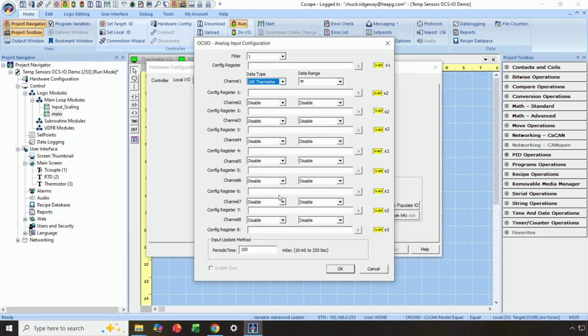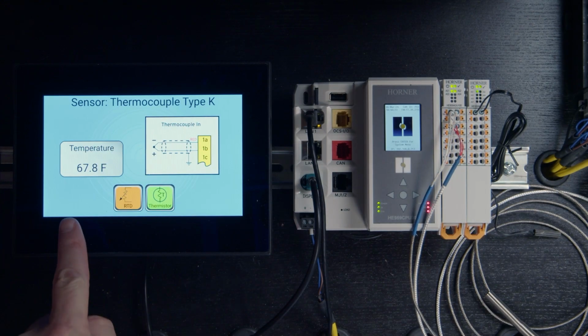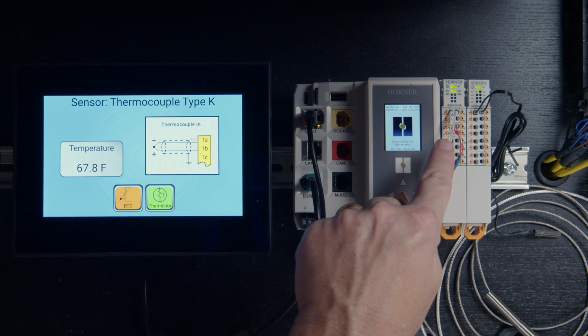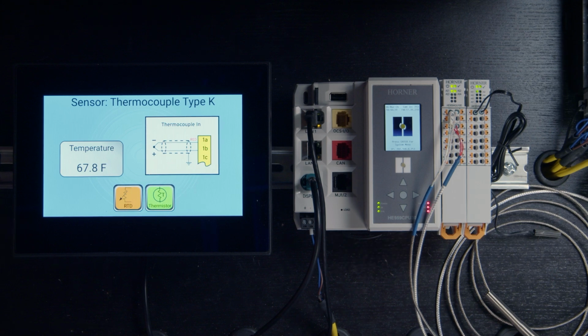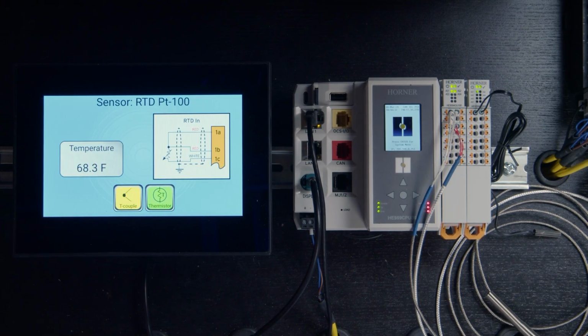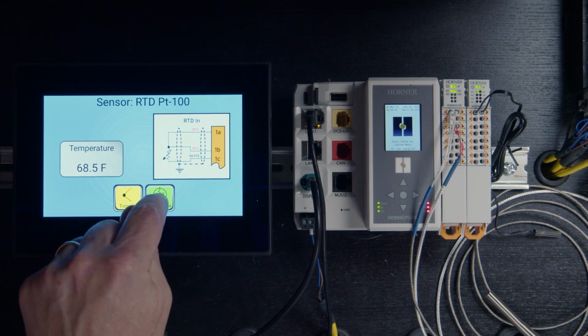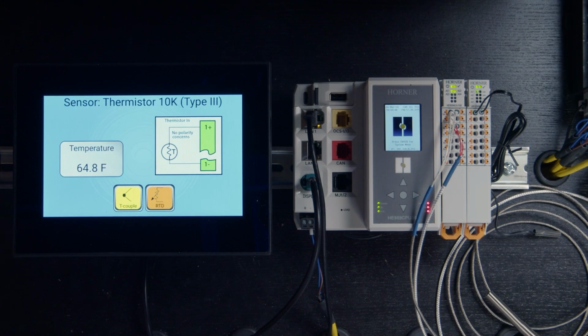Okay, all right, let's take a look at just real quickly what I've got going on with my demonstration on the bench. Okay, so here's my thermocouple reading. You can see I've got a thermocouple connected here, just connected to this probe here. When I touch the probe, you can see my temperature values go up as it heats up. All right, I've also got my RTD sensor connected here. Again, just measuring the ambient temperature in my bench area. And then I've also got my thermistor as well. So really pretty simple to apply these temperature sensors to the Horner OCS-IO system.